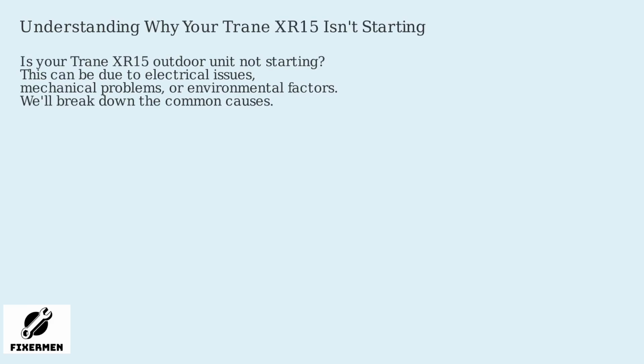Is your Trane XR15 outdoor unit not starting? This can be due to electrical issues, mechanical problems, or environmental factors. We'll break down the common causes and how to troubleshoot them.